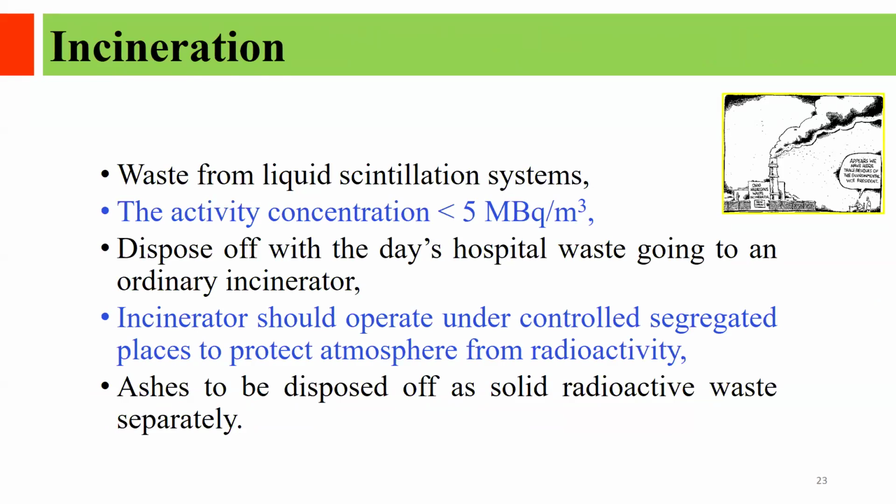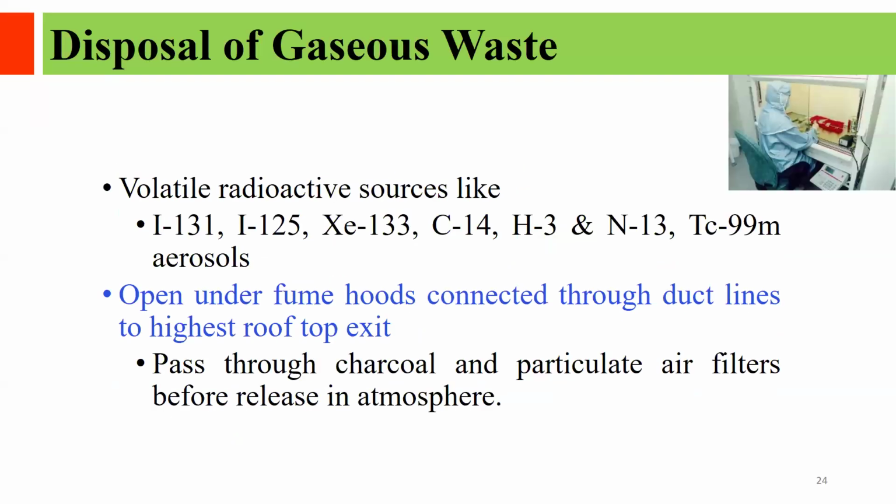Incineration is also one of the ways where the management of waste takes place. It is generally for the waste generated from liquid scintillation systems. Activity concentration should be less than 5 megabecquerel per meter cube, and it can be disposed of with the day's hospital waste going to an ordinary incinerator. Incinerators should operate under controlled, segregated conditions to protect the atmosphere from radioactivity, and whatever ashes are generated during incineration have to be disposed of separately as radioactive waste.